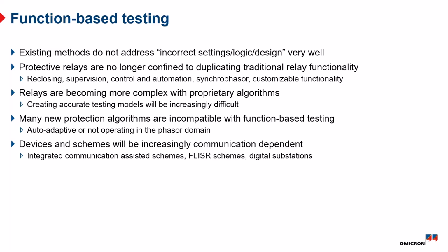These new relays, the SEL T401 is a good example, we're not actually using these phasor quantities anymore. We're actually using a transition from pre-fault to fault in something called incremental quantity. So it's a more complex calculation. The problem is you can't test it with a traditional function-based relay. You have to test it with full simulation because you have to hold the source impedance constant when you transition from pre-fault to fault, etc. So there are some challenges coming along based on how smart these relays are becoming.